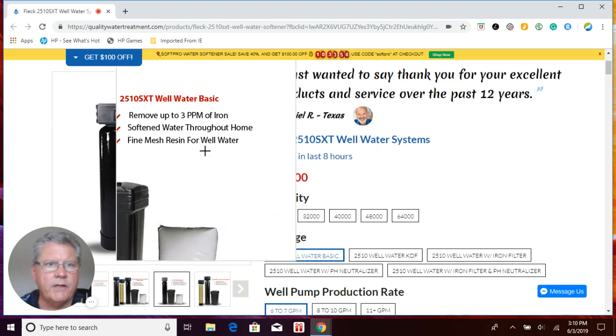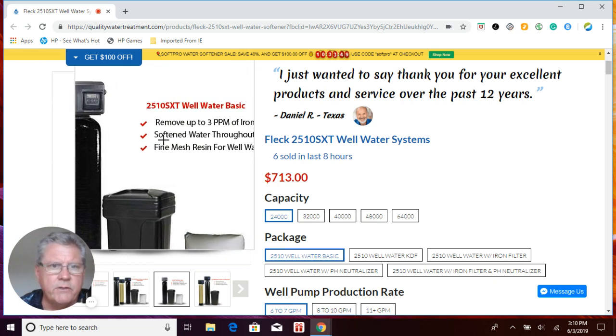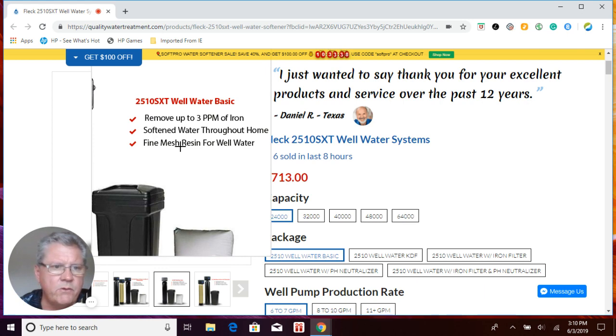We're going to start off with our Fleck 2510SXT Well Water Basic, which is a water softener. What we've done here is used a gravel under-bed with a fine mesh resin for well water. Fine mesh resin has more surface area than your standard resins, so it's able to remove more iron and doesn't foul out as easily. It'll remove up to three parts per million of what we call clear water iron. Some claim up to five parts per million, and yes, I've seen systems do that under perfect circumstances, but the rule of thumb is just three parts per million. Anything above that, you really want to use an iron filter along with your water softener.